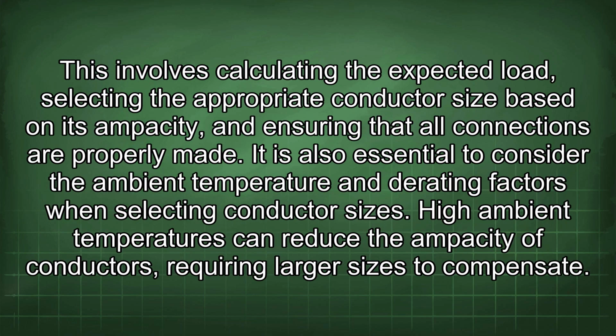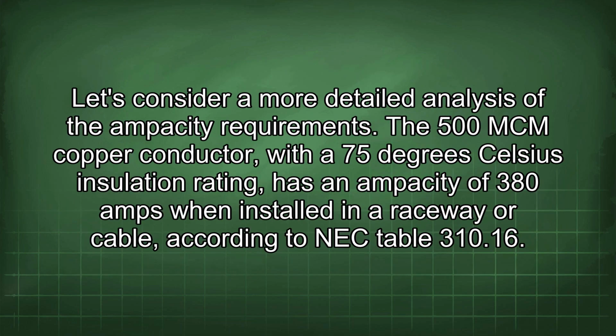This involves calculating the expected load, selecting the appropriate conductor size based on its ampacity, and ensuring that all connections are properly made. It is also essential to consider the ambient temperature and derating factors when selecting conductor sizes. High ambient temperatures can reduce the ampacity of conductors, requiring larger sizes to compensate. Let's consider a more detailed analysis of the ampacity requirements.